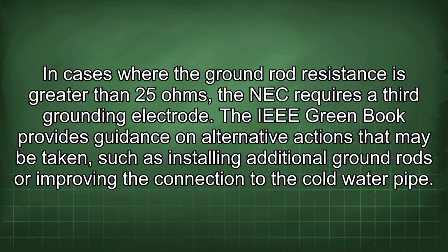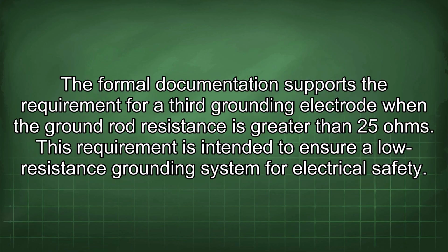In cases where the ground rod resistance is greater than 25 ohms, the NEC requires a third grounding electrode. The IEEE Green Book provides guidance on alternative actions that may be taken, such as installing additional ground rods or improving the connection to the cold water pipe. The formal documentation supports the requirement for a third grounding electrode when the ground rod resistance is greater than 25 ohms. This requirement is intended to ensure a low-resistance grounding system for electrical safety.